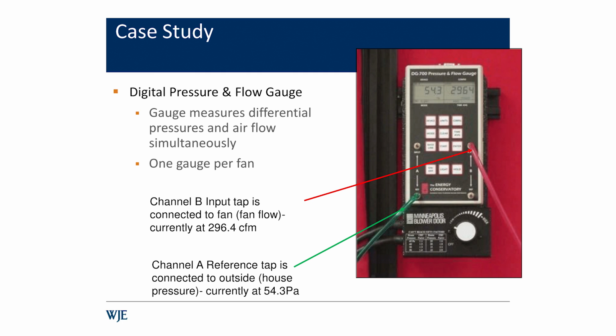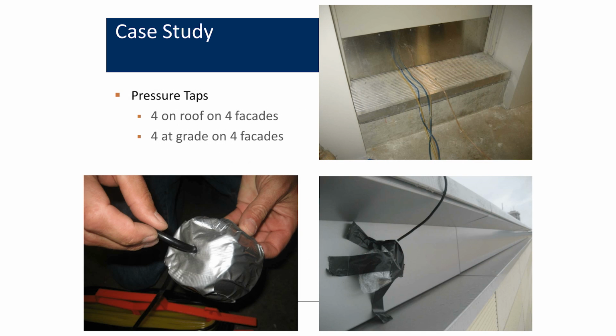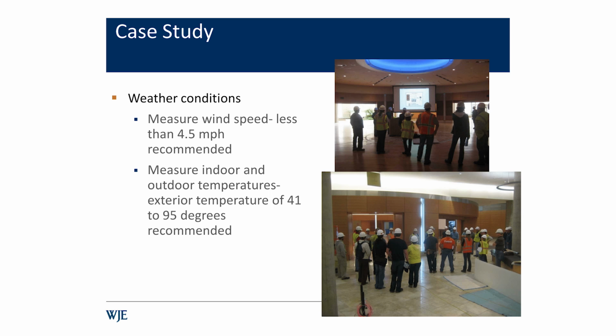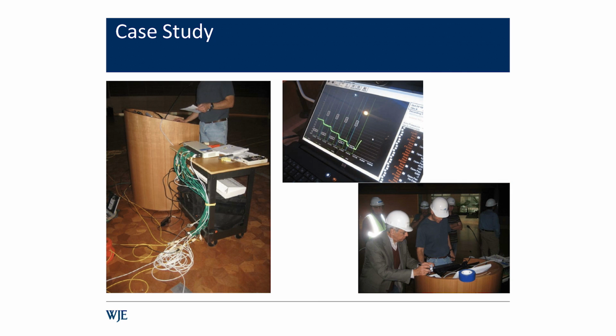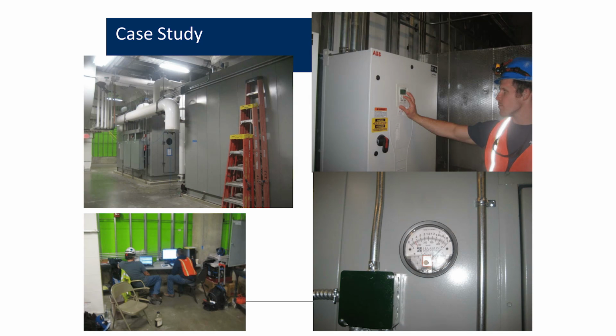And then we had our DG-700 micromanometers that were measuring the airflow and the differential pressure simultaneously at the fans. We had our pressure taps at the roof and at the grade on all 4 facades, and we tried to shield those from the wind. We had the weather conditions that we needed. Our wind speed was below 4.5 miles per hour, and we had the right exterior and interior temperature difference. And then all those fans routed back to this DDC control system that simultaneously calculates the air leakage rate with the pressure differential between inside and outside. So it calculates the air tightness and then characterizes the leaks. We also got to use the air handling system for this test as part of the research project.